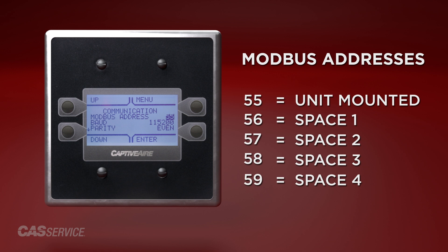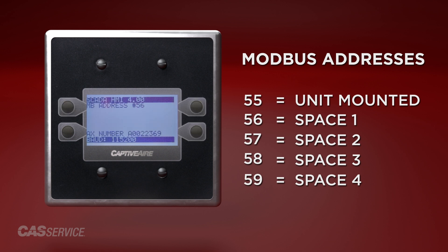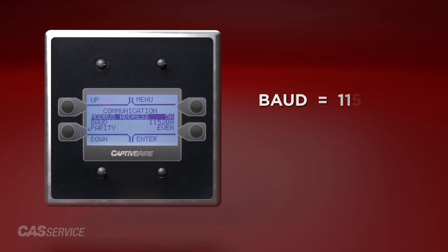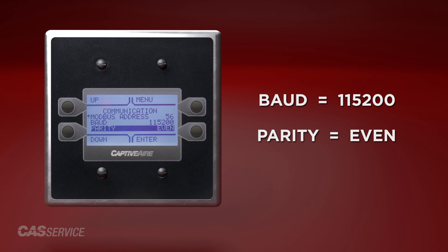If a change is made in the communication section, you will be prompted to save this change as you click menu to back out. The baud rate and parity should always be set to the default of 115,200 and even.